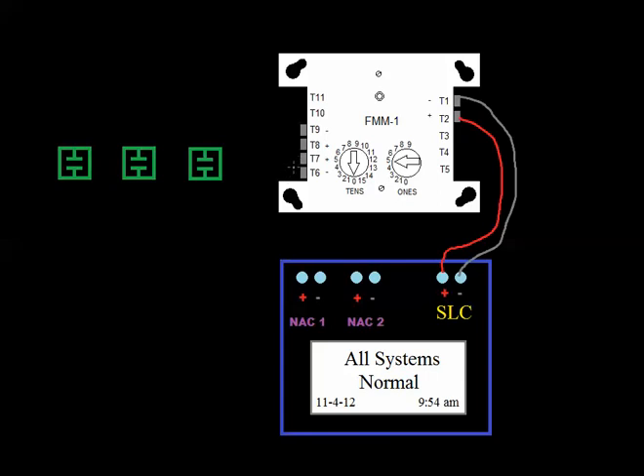If it's a horn circuit, it's not technically called class B. There's different classes. But basically, the difference between class A and class B is if you have, let's say I just have power out of this module, or if it were a conventional circuit, you know, power in and out of each device, and then at the end, I'd have an end-of-line resistor, right?